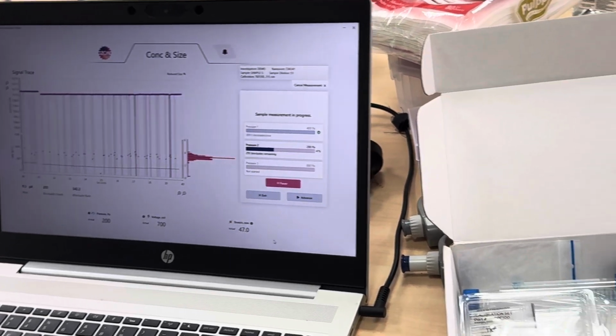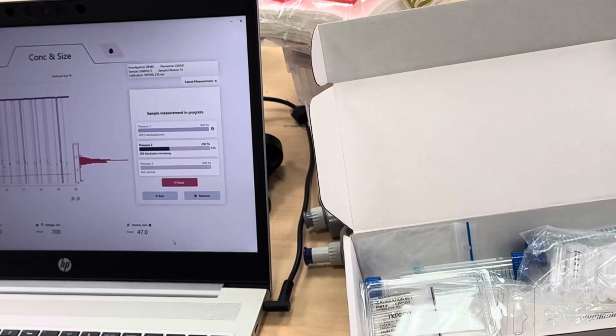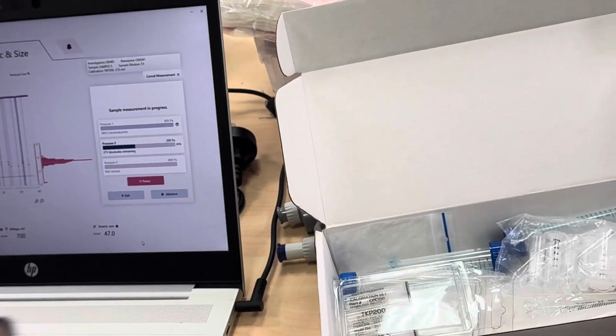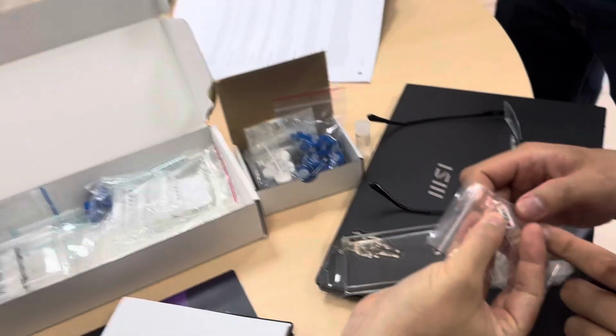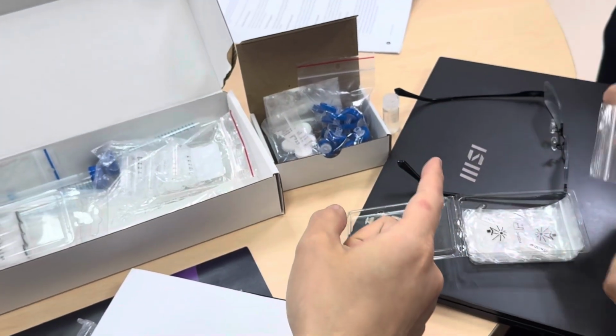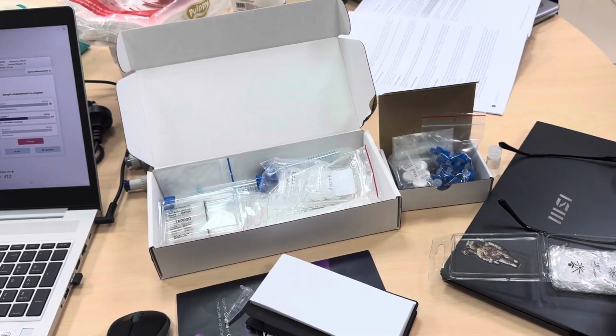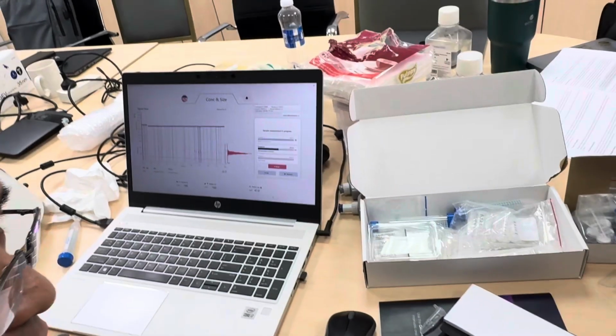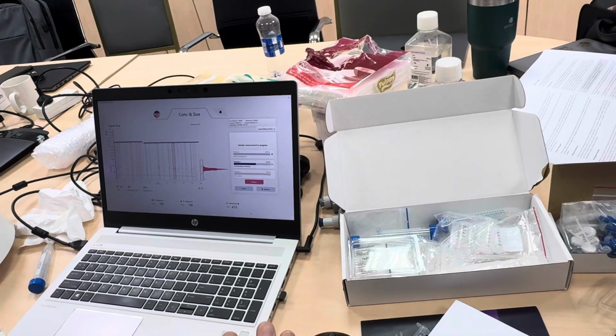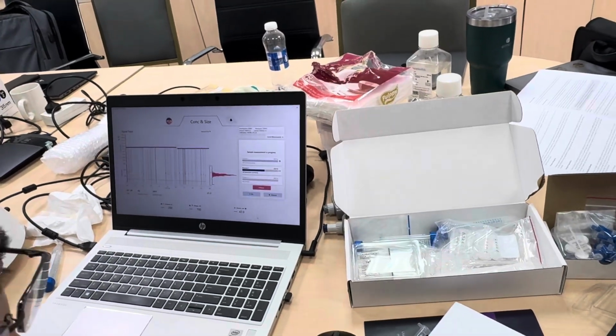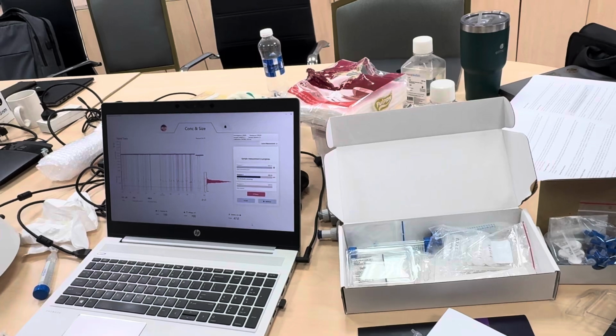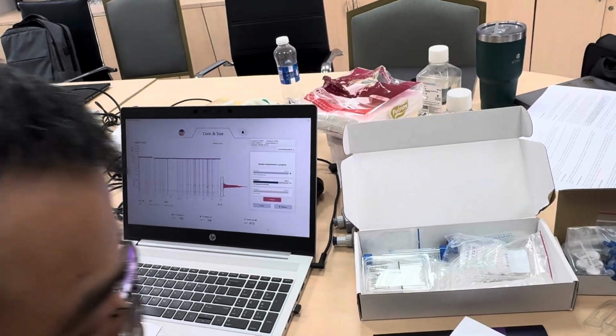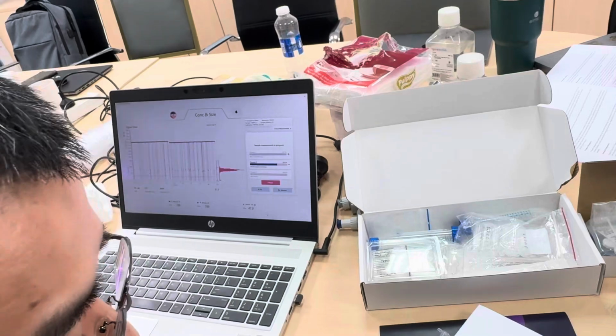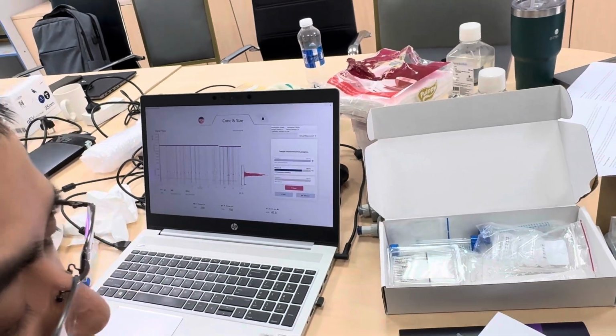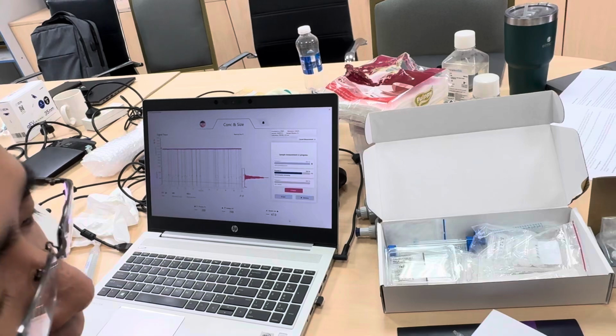Can I check the information? Yeah. Based on this number, this is the median measuring range. So this one is the best. Usually we know that the exosome average diameter is around maybe 100. So usually we use, say, MP 100 or MP 150 to analyze it. This one is the serial number, so it's used for our QC purpose. There's no information here, so it's just for our record.